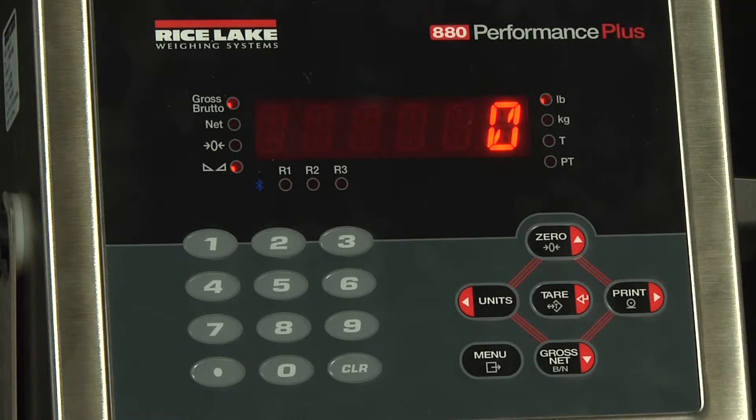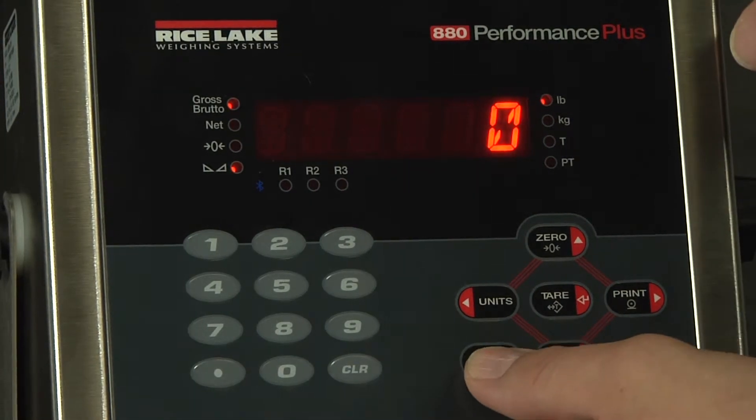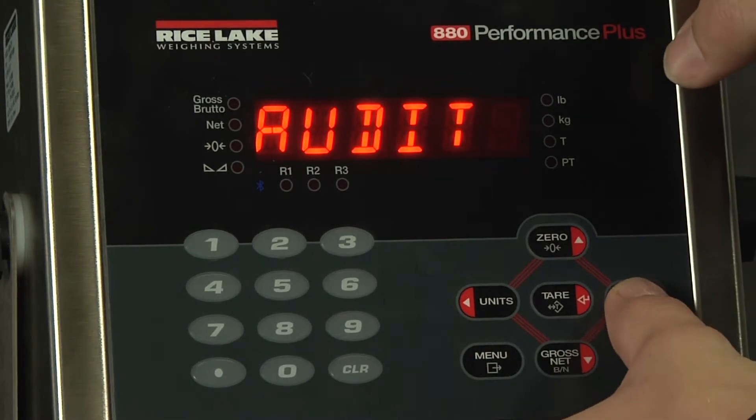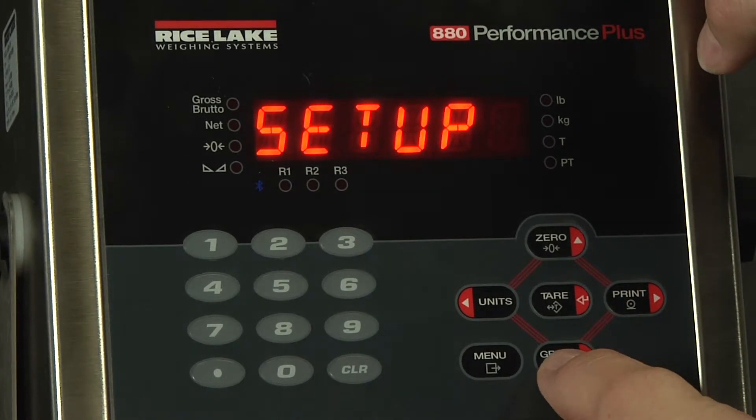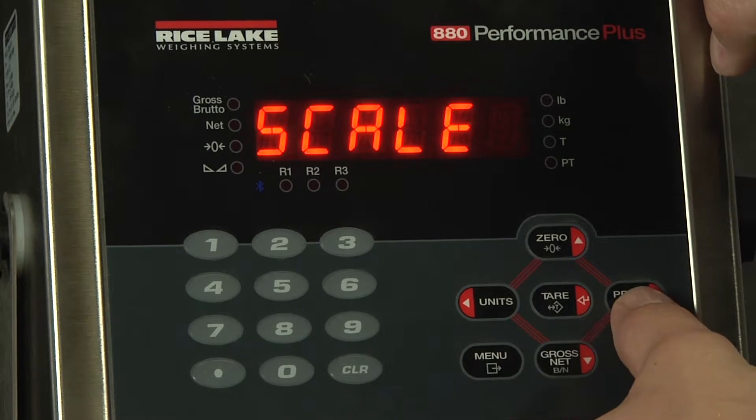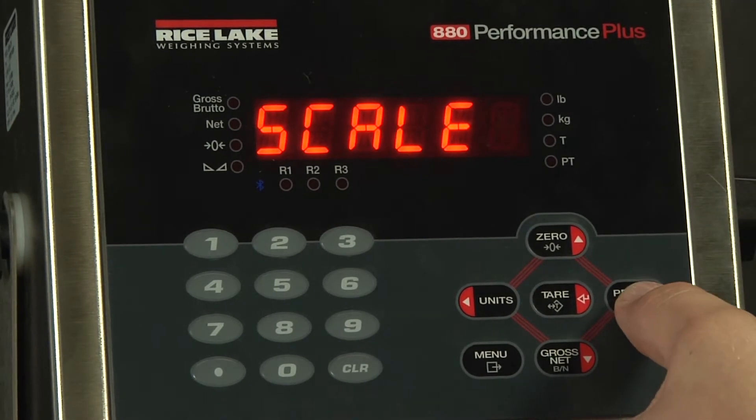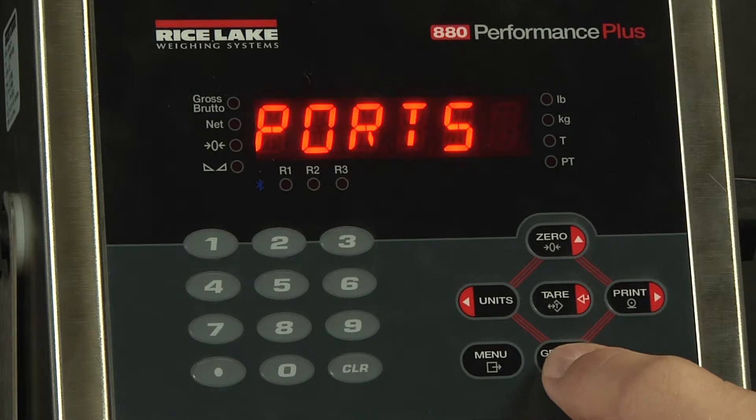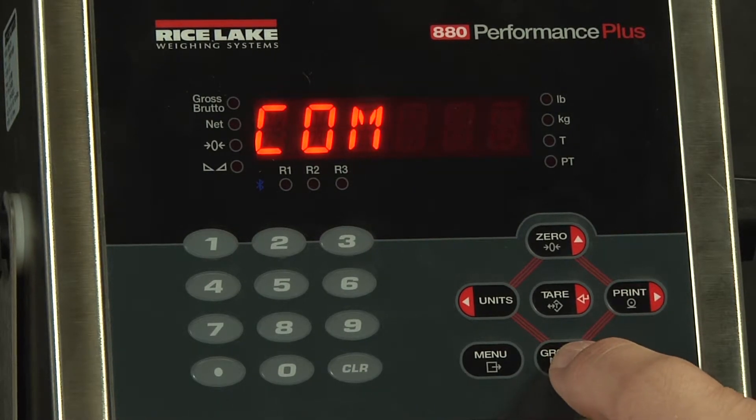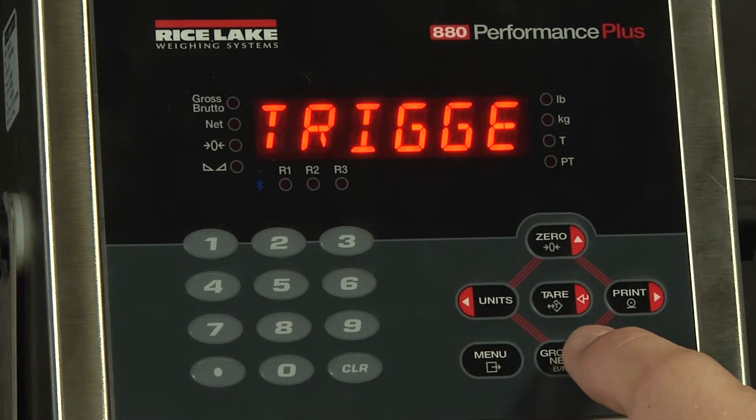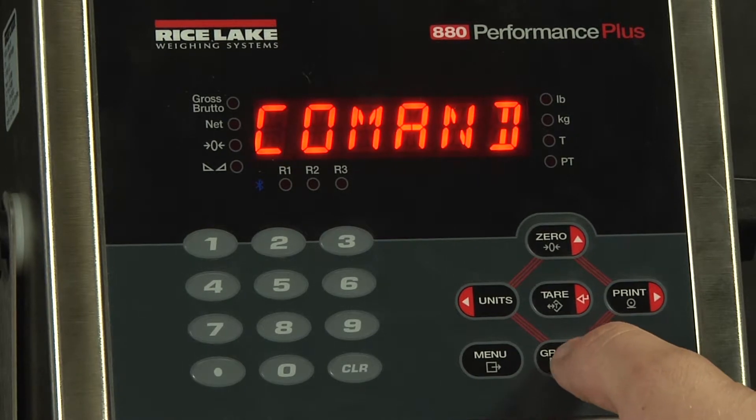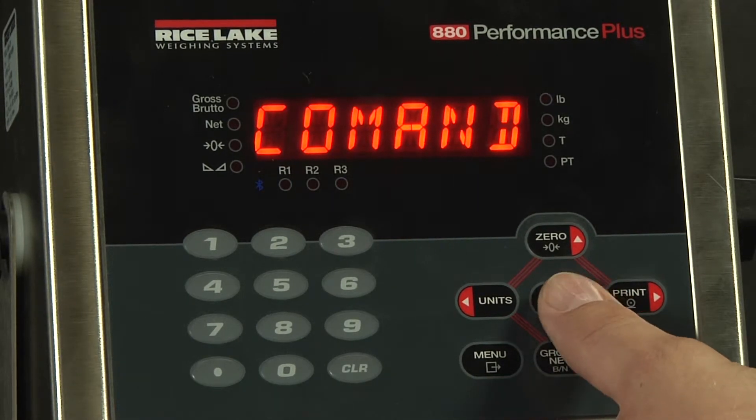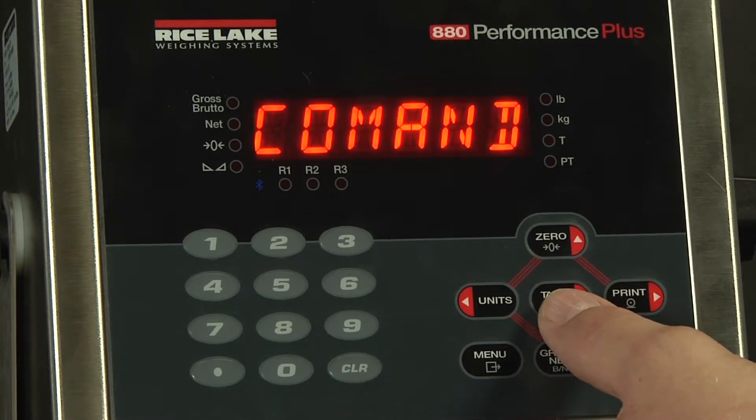Now on the other side we will also check the indicator. We go to setup and drop down. From here we see scale. We will now scroll over to ports and drop down again. Under COM port we now have the trigger. This needs to be set to command in order for it to receive commands and output a response.